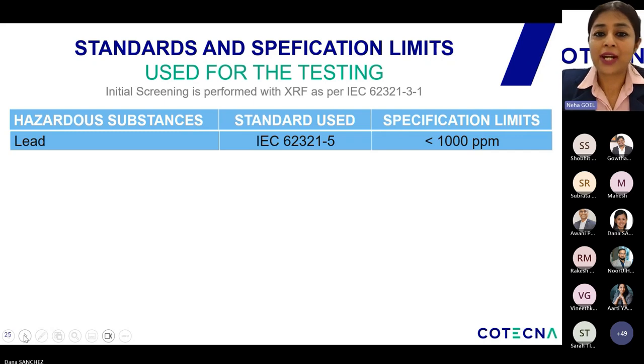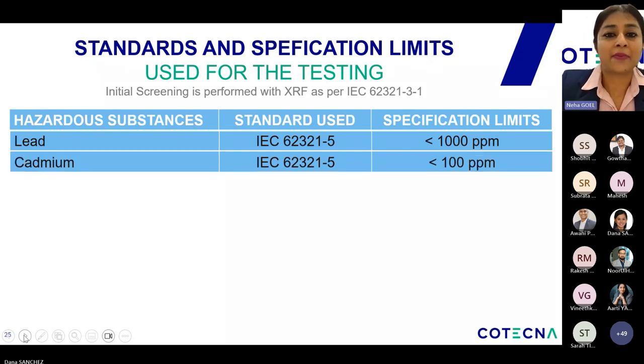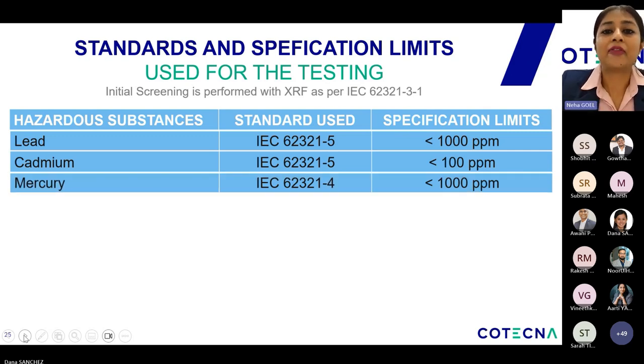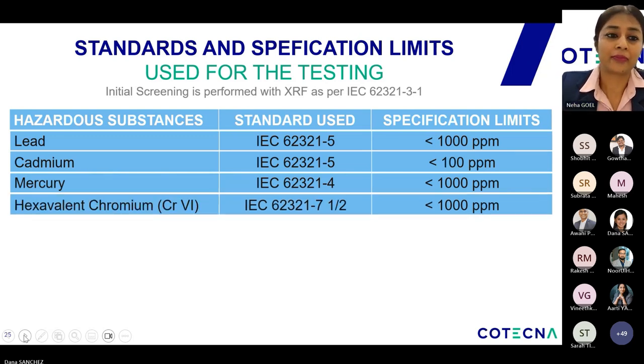The hazardous substance list is tested with the standard IEC 62321-5. Cadmium: for cadmium, we are using the standard IEC 62321-5 again. For mercury, we are using the standard IEC 62321-4. For hexavalent chromium, we are using IEC 62321-7, which is divided into two parts, part 1 and part 2. Part 1 comprises the detection of hexavalent chromium in metal parts, and part 2 comprises the detection of hexavalent chromium in polymers and electronic parts.